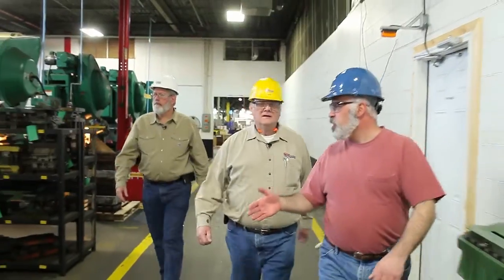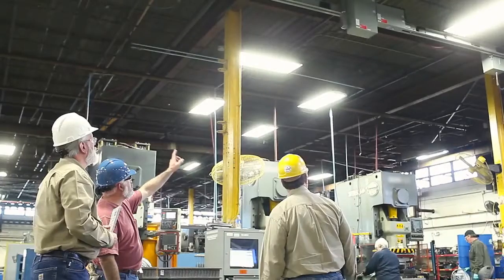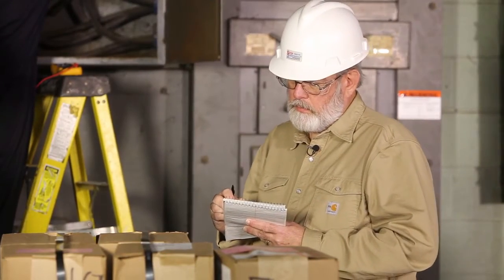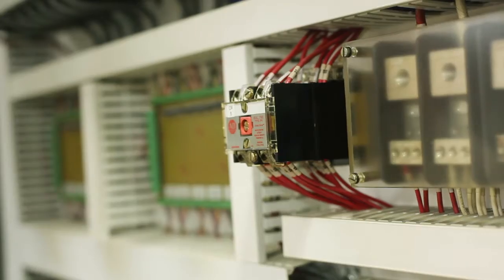The site surveyor will collect a history of equipment breakdowns or issues, walk through your site, documenting observations on grounding and bonding, main electrical service entry, power distribution, and inspection of electrical equipment. Diagnose the issues and formulate a treatment plan, complete with a list of surge protection and grounding recommendations.